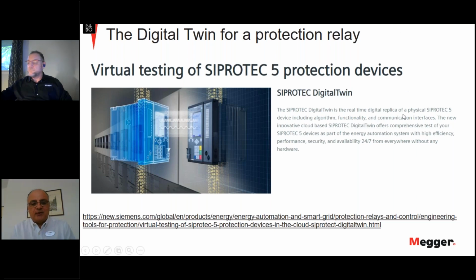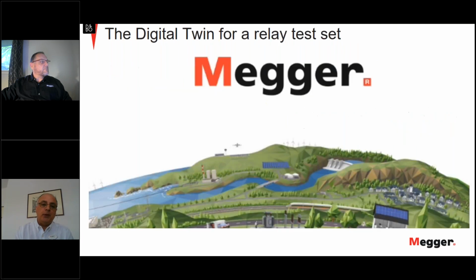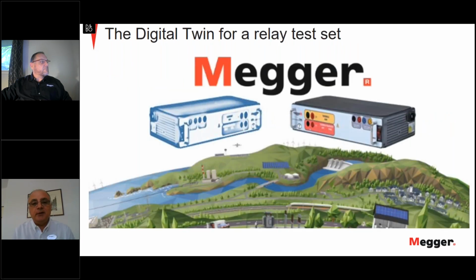Yes, thank you. Very nice presentation, very interesting. I have now the honor to introduce you for the first time to a digital twin for a relay test set. But we must start with a digital twin for a protection relay. SIPROTEC 5 protection devices have developed a completely full digital twin, which is a software replica of the protection algorithms in the physical relay. And we have done a digital twin for our relay test set, SMRT series. So the blue one is actually the ghost of the real test set.